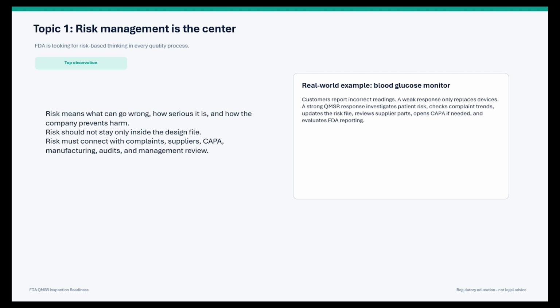The company would check whether similar complaints are increasing. It would review whether the risk file needs to be updated. It would check whether supplier parts or manufacturing variation contributed to the problem. It would open CAPA if the issue shows a recurring or systemic weakness. It would also evaluate whether FDA reporting is required. From an inspection readiness perspective, the question is not simply whether a risk file exists. The question is whether the risk process is alive and being used when real product problems appear.